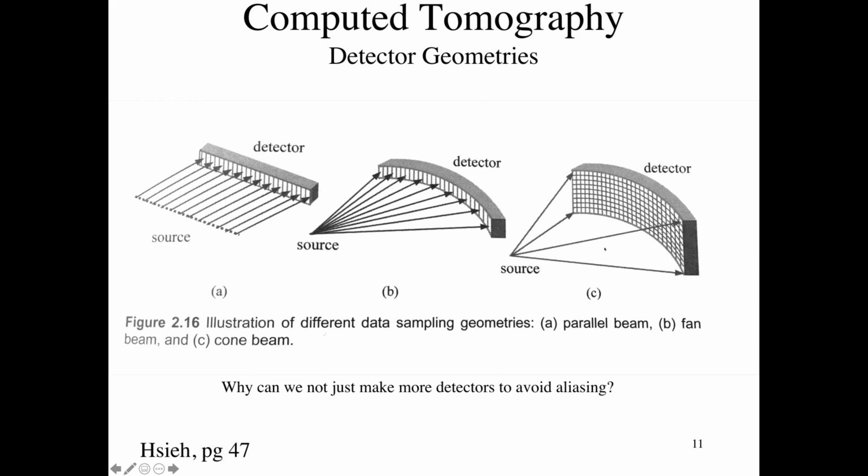Modern CT scanners, like in the last 5 years, or maybe in the last 10, 15 years, everybody that's buying CT scanners has not just one row of detectors, they have a whole set of detectors stacked one on top of the other. So it's a 2D array. It's like if I had 64 of these, I've got 64 simultaneous CT scanners going, of the old school. So it really increases your data rate in terms of acquiring data in the Z, or the slice, direction. I get those slices almost simultaneously.